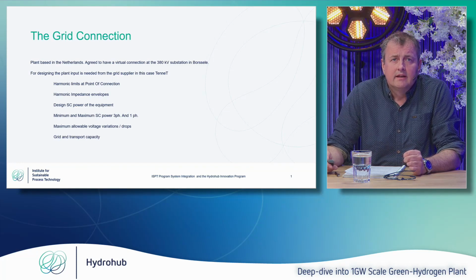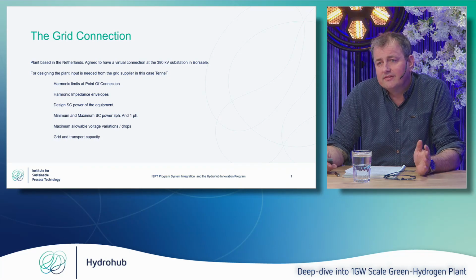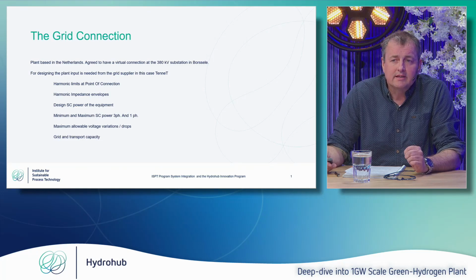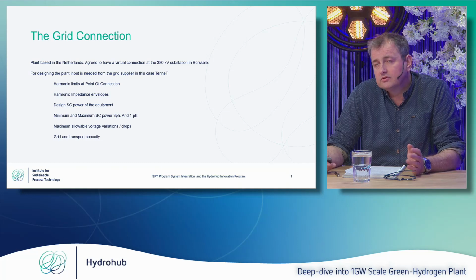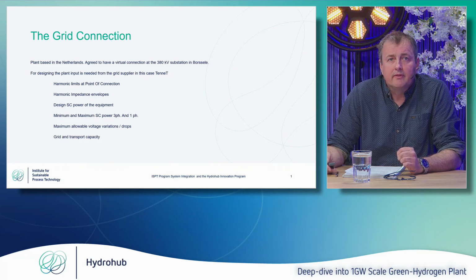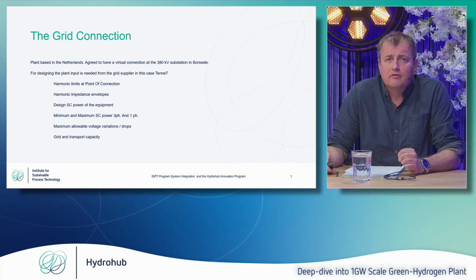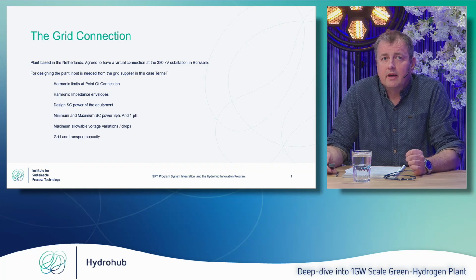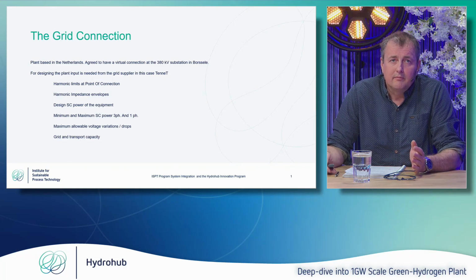Of course, the design short circuit power of the equipment is needed in order to select the correct equipment. Minimum and maximum short circuit power, 3-phase and 1-phase, is needed. You need this for selecting the proper protections, but also for making short circuit calculations, and in order to select the proper equipment. Of course, maximum allowable voltage variation, voltage drops, what is still okay for the grid supplier. And based on that, you need to do your calculations. And of course, the grid and the transport capacity is very important.